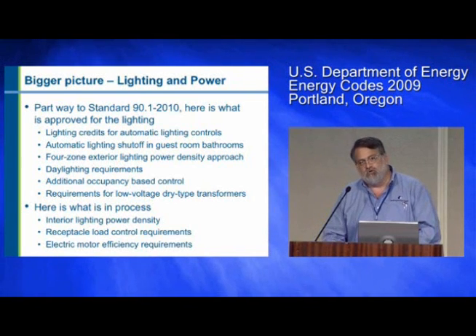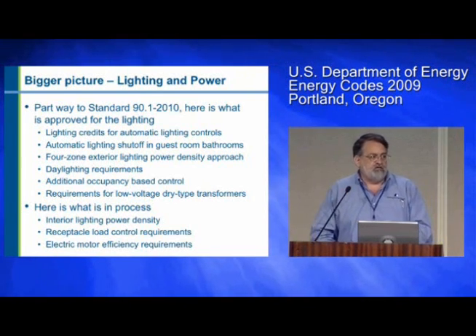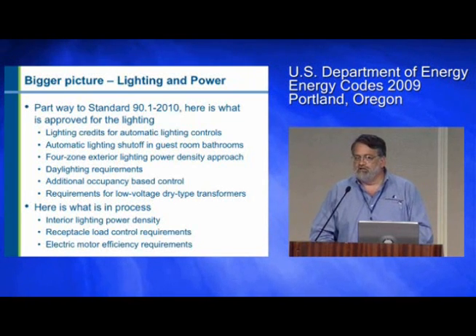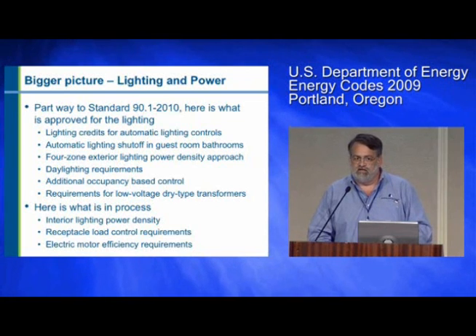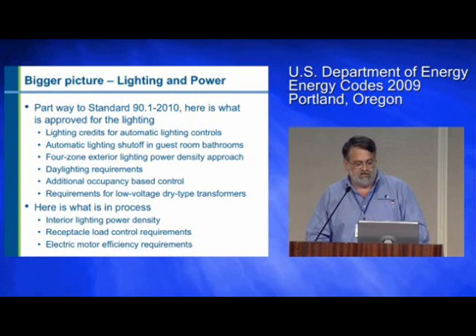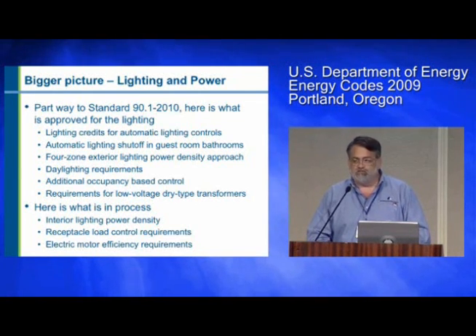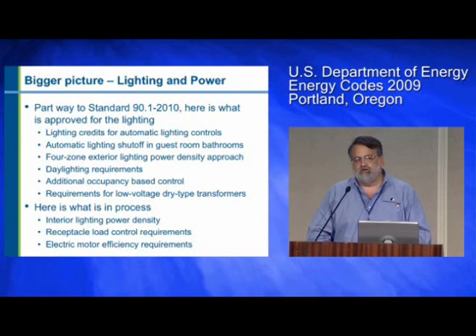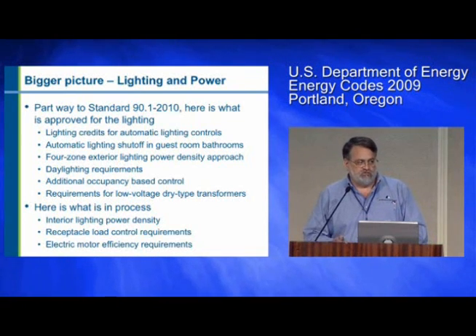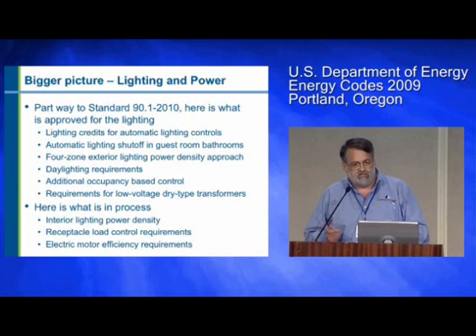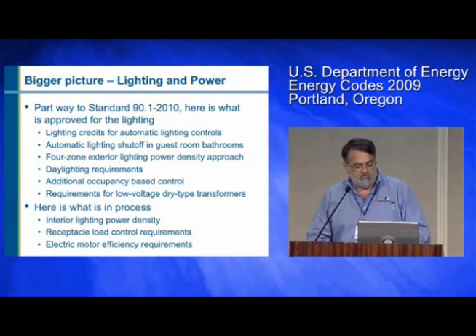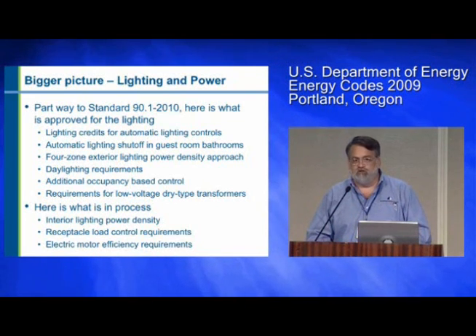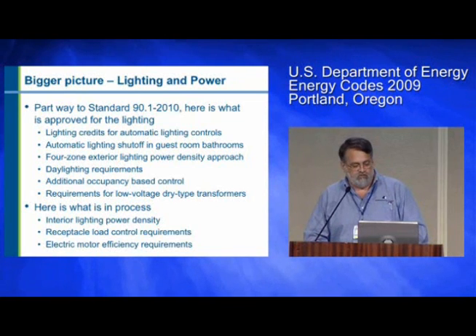Daylighting requirements, as Mark mentioned, there is now a requirement to put in skylights where it's applicable in a building. There are also requirements to control lighting when you have daylighting, and I'll go over those in a little more detail. Additional occupancy-based control. For the last several years, there has been requirements for certain space types to have occupancy sensors as part of the control for lighting. That's going to be increased. There will be more spaces that require that specific control. There are also requirements for low-voltage dry-type transformers that essentially mimic federal regulations.